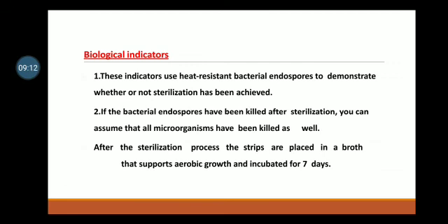Biological indicators. These indicators use heat resistant bacterial endospores to demonstrate whether or not sterilization has been achieved. If the bacterial endospores have been killed after sterilization, you can assume that all microorganisms have been killed as well. After the sterilization process, the strips are placed in a broth that supports aerobic growth and incubated for 7 days.